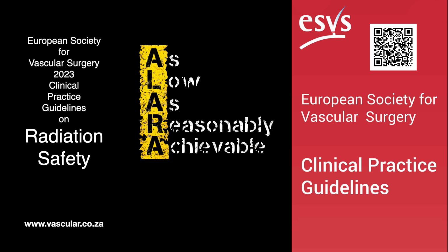And the dose savings can be substantial. Studies estimate up to a 2.5-fold dose saving compared to conventional magnification, or around a 30% reduction compared to just switching to the next smaller FOV. One study in coronary procedures found non-inferior visibility with digital zoom compared to conventional mag, but with about a 30% saving in air kerma and KAP. So the recommendation is clear. Yes. Recommendation 20 is Class 1, Level C. Digital zoom and appropriately sized high-resolution monitors are recommended over conventional FOV-based magnification whenever possible.